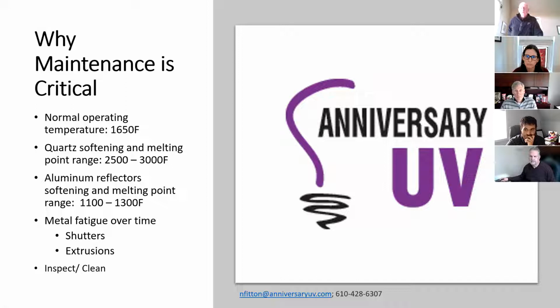Why is maintenance so critical? Well, as I mentioned, you're dealing with extremely high heat. Quartz softens and melts at 2,500 to 3,000 degrees Fahrenheit. We will get there quickly within a minute or two without cooling. The aluminum reflectors on most systems actually soften and melt at a much lower point at 1,100 to 1,300, and the lamp is normally operating at 1,650. So why aren't the reflectors melting? Well, sometimes they do, but if your cooling system is working correctly, your reflector sits an inch or two behind the back of the lamp, and the cooling prevents that high lamp heat from reaching your reflector.